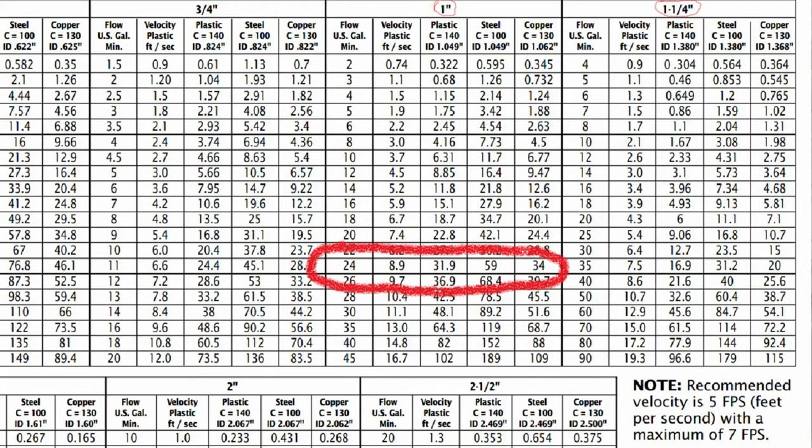So if we look at the chart for one inch pipe, the velocity for 24 gallons a minute is 8.9, which is more than seven. So we'll go over to the inch and a quarter chart and for 24 gallons a minute they list 25. For 25 our velocity is 5.4, which is good. We also want to take note of the friction loss in plastic pipe, which is what we'll be using because we'll need that later: 9.06.